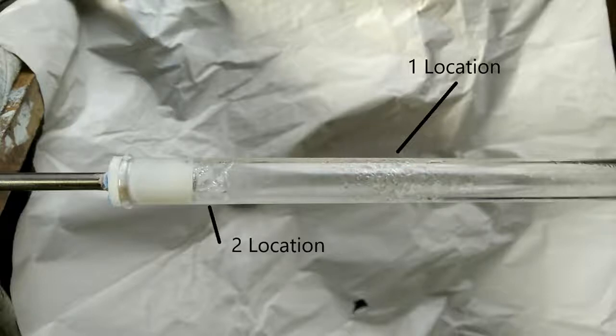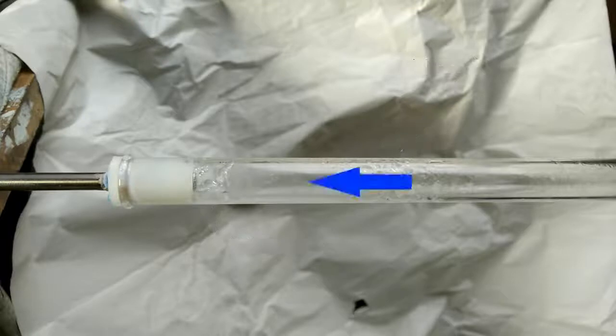The second location is where the pitot tube outlet is, and condensate is evident in much greater quantities. What you will see is condensate moving along the wall of the expansion tube in the opposite direction to flow, moving towards the orifice.